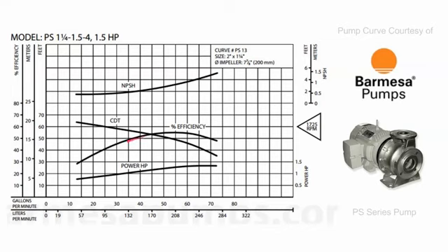So you can see here that in the high head applications, this pump is not very efficient. However, as we increase the amount of flow that we're trying to push with this pump, thus moving more water per rotation of the pump's impeller, we increase the efficiency until we kind of peak out right about here, and then we start to decrease the efficiency again.